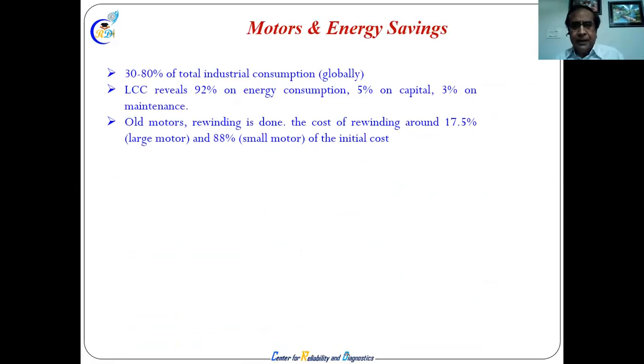So for a critical asset like a motor, energy saving is 30 to 80% of total industry globally, if you see, and in life cycle costing, 92% is energy consumption itself. Okay, 5% is capital, 3% is exclusive maintenance, and 90% is energy consumption. This motor, if it is not maintained, this is only maintenance cost, labor, spares and other things. This energy can be reduced much more if you take proper care. Electrical unbalance should not be there. Okay, eccentric gap should not be there. Both bearing points of the motor should run properly. It should not be eccentric. We have seen a lot of motors with eccentric bearings, and they take a lot more energy than they are supposed to.